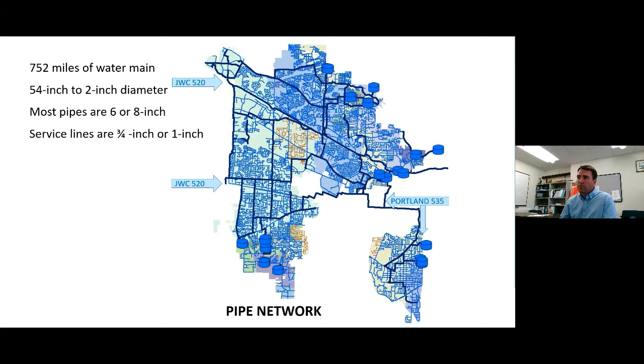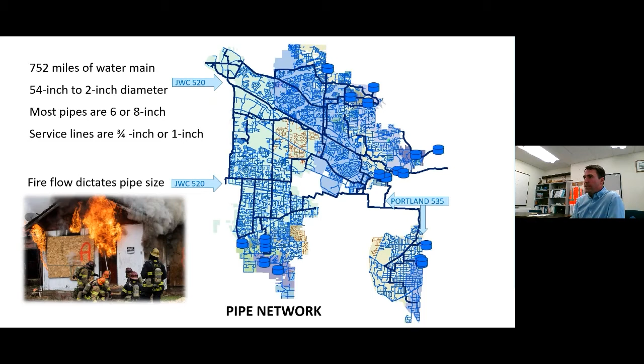Now, the size of those pipes, typically the 6 or 8 inch, is dictated by the fire flow we need to deliver. So when the fire department shows up and needs to flow a bunch of water, we need a large enough pipe to deliver that. If we didn't have a fire protection aspect to what we do as a district, and all we had to serve was drinking water, we could do that through a smaller diameter pipe, because folks using water in their homes is a much lower demand on those pipes, and they wouldn't need to be as large. But obviously we provide fire protection, and we need to have that capacity available whenever it's needed.